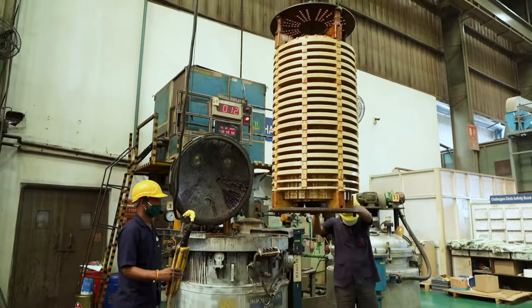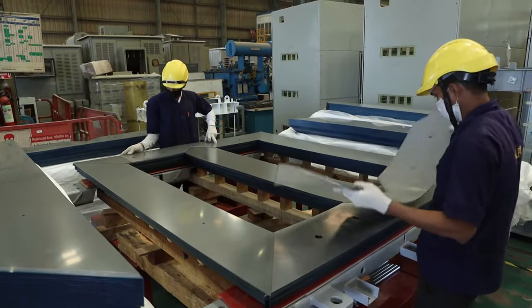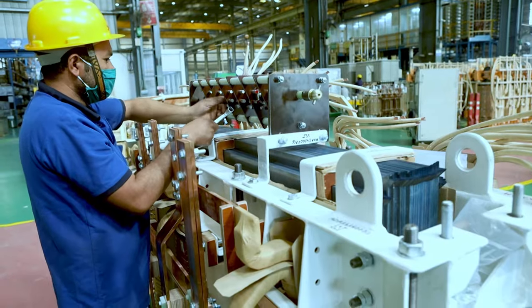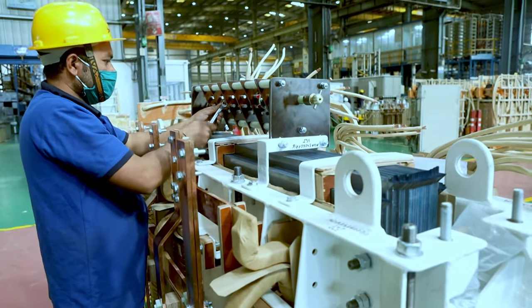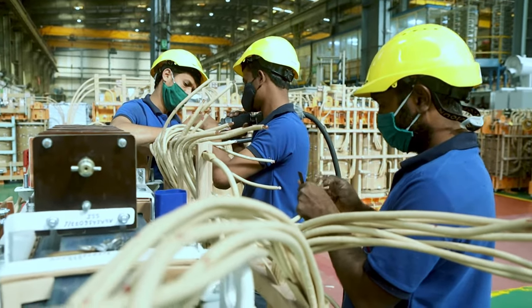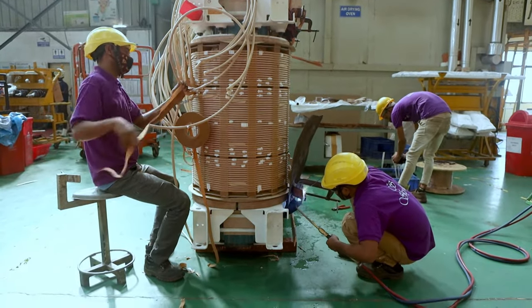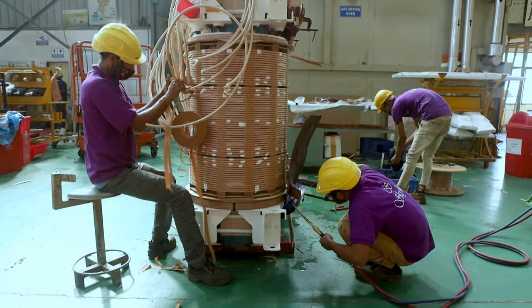After this, the next step is core coil assembly wherein thin sheets of CRGO are assembled to make the core. After opening the top yoke, we put low voltage and high voltage winding in each limb and assemble the top yoke again. Then we connect all three phases per the transformer application and the core coil assembly is made ready.